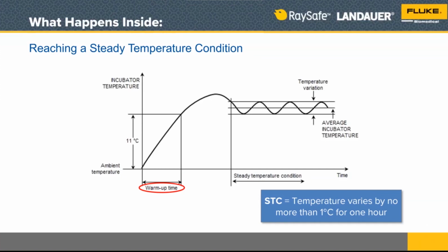When we first turn on the incubator, there's a test that we do that is about the warm-up time. And the warm-up time is actually the amount of time that it takes to get from ambient temperature, which is the room temperature. We need an 11 degrees C rise in that warm-up time. We're going to measure how long it takes to get that 11 degrees C rise. And of course, it's from ambient, meaning room temperature. That's what the warm-up time is all about. And the reason we want to take a look at that is it's important that we understand that heating element is actually going to warm up that incubator chamber. And the specification of 11 degrees C in a specific time is really important.